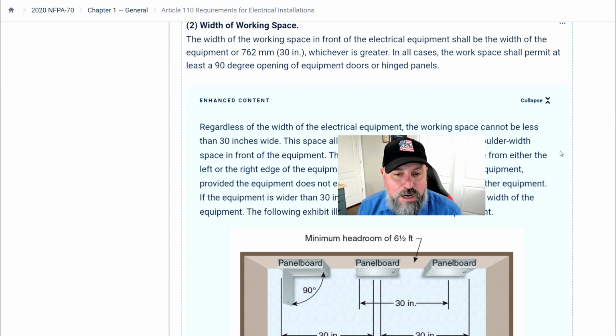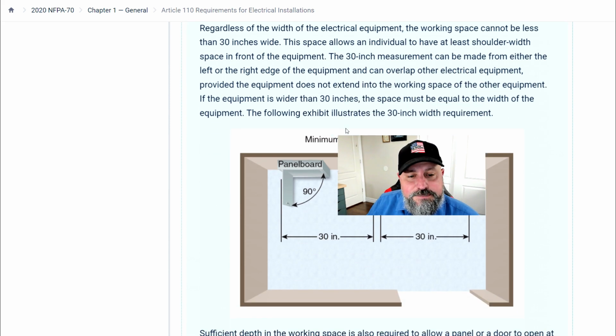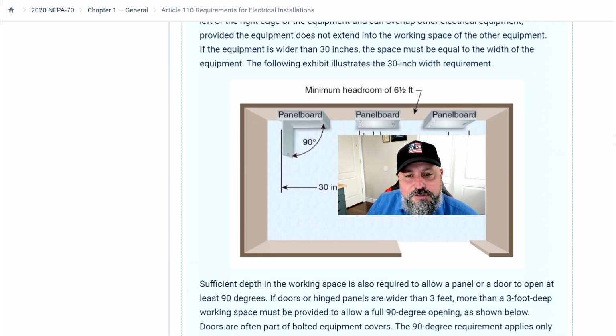If the equipment is wider than 30 inches, the space must be equal to the width of the equipment, following the exhibit, and 30 inches. And I just wanted to go back here. So you've got to also make sure that the doors can open 90 degrees. So that's a big one. If it has a door on it, it has to be able to be open 90 degrees. But here it shows the 30 inches, and you've got to have 30 inches of space. They can overlap. Minimum headroom of 6.5 feet, 90 degree here, 30 inch, overlap 30 inch, and then there's your 30 inch there with the 90 degree.